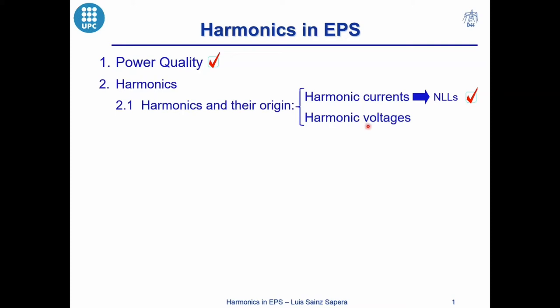We should remember that the origin of harmonic currents is the nonlinear loads which consume periodic but non-sinusoidal currents. These currents can be decomposed into several sinusoidal currents of different frequencies. The current of the same frequency as the original one is the fundamental current, while the other sinusoidal waveforms are the harmonics which are introduced in the network by nonlinear loads.